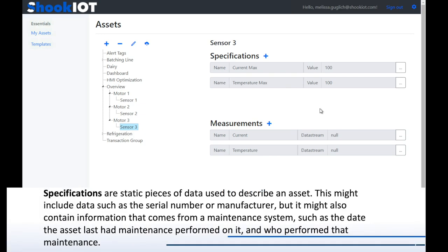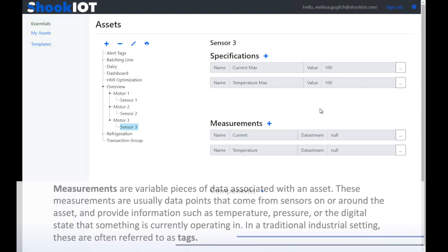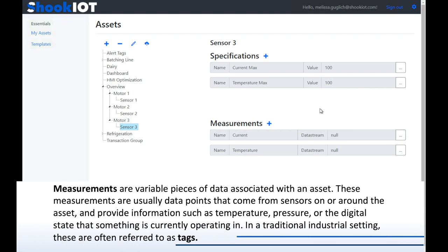Specifications are static pieces of data used to describe an asset. This might include data such as the serial number or manufacturer, but it might also contain information from a maintenance system, such as the date the asset last had maintenance performed on it and who performed that maintenance. Measurements are variable pieces of data associated with an asset. These measurements are usually data points that come from sensors on or around the asset, providing information such as temperature, pressure, or the digital state that something is currently operating in. In a traditional industrial setting, these are often referred to as tags.